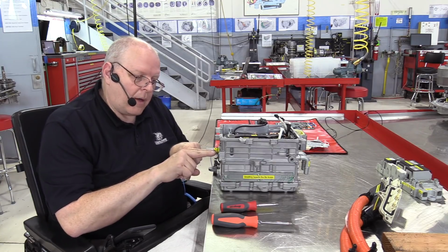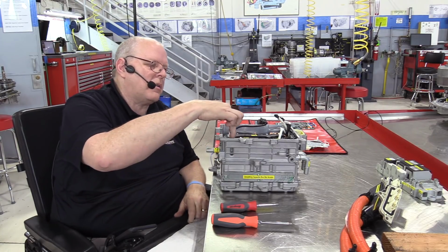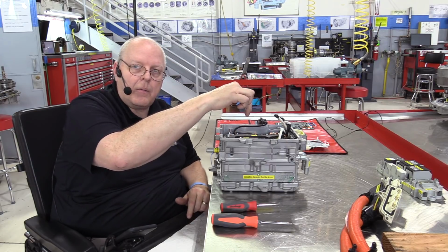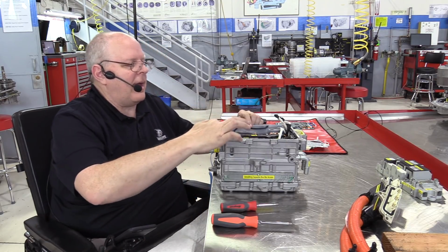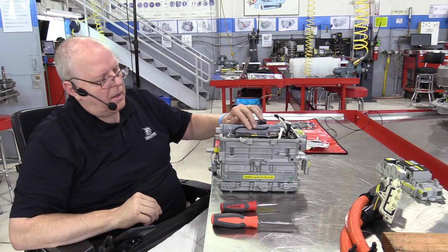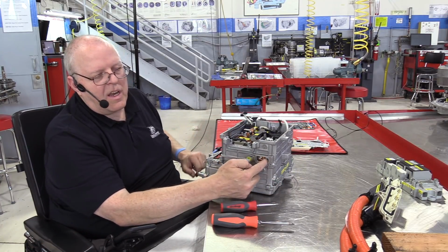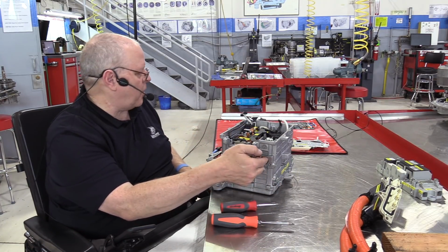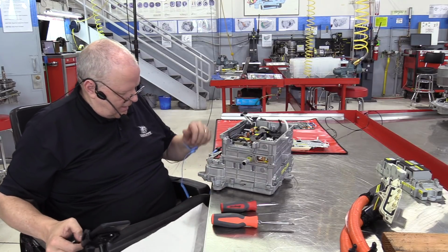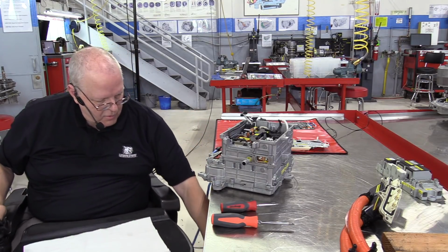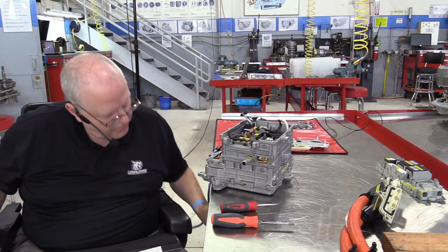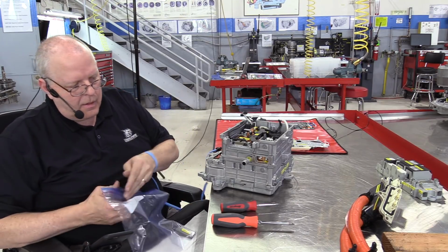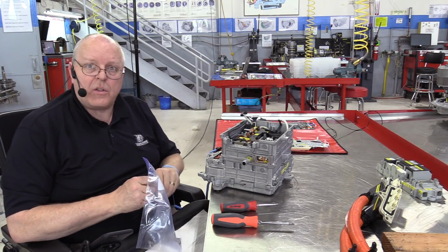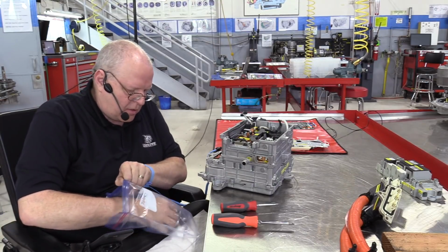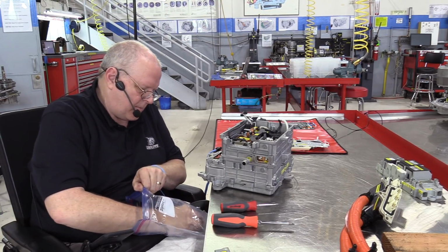Okay, I connected the lower bus bars to the boost inverter module up here and the negative bus bar. The 2 connections for the lower bus bar to the upper bus bar are right here, and there's a cover that covers that up. This cover should be sealed with the form-in-place gasket sealer as well.